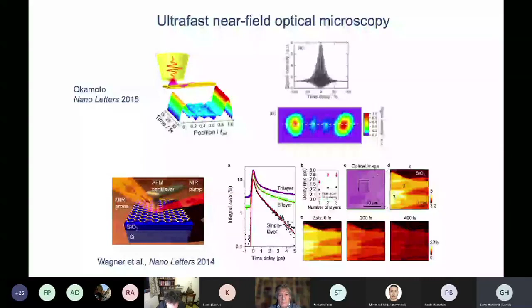And so in these experiments, you take a laser system, typically a high repetition rate laser. You make a pump and a probe beam. You modulate the pump beam at a very high frequency using, we use an acousto-optic modulator, or you could use an electro-optic modulator. Then you focus the two beams at a sample. So if you use a very high numerical aperture objective, you can, of course, get high spatial resolution. And the other thing about this is that when you focus the beam to a small spot at the sample, you get increased sensitivity too.